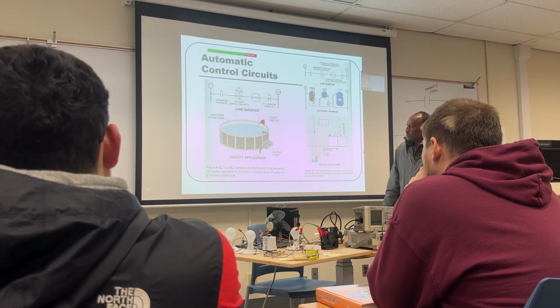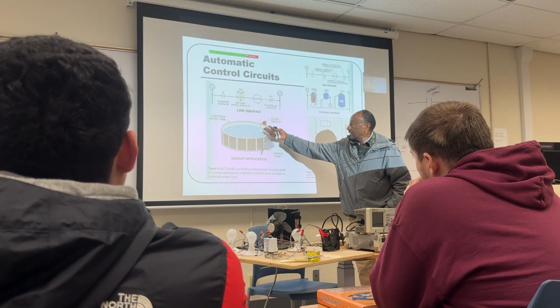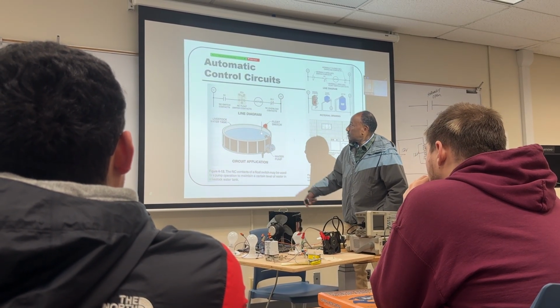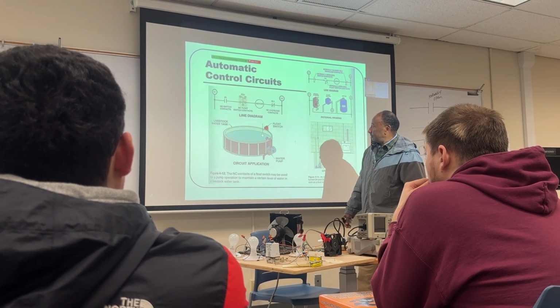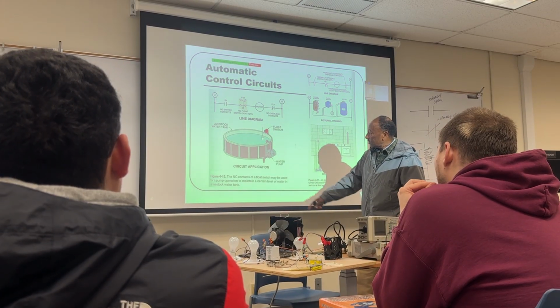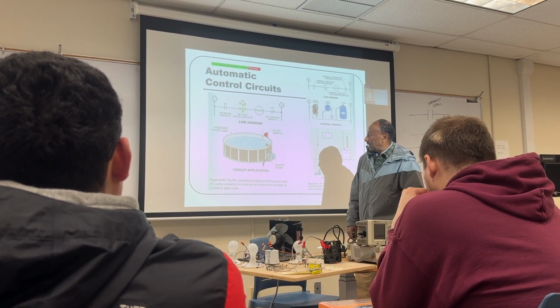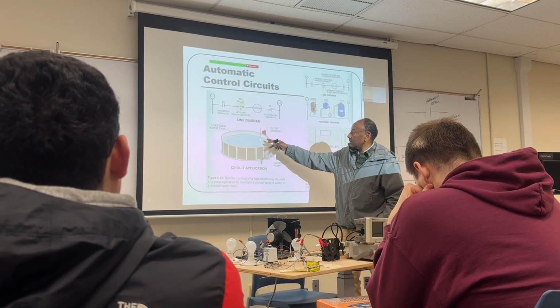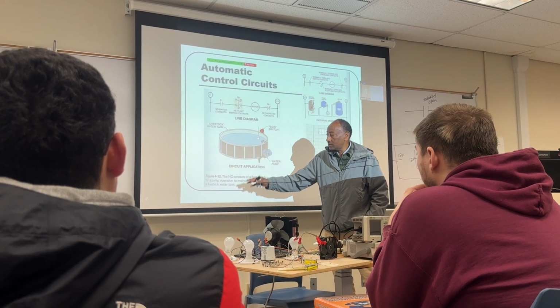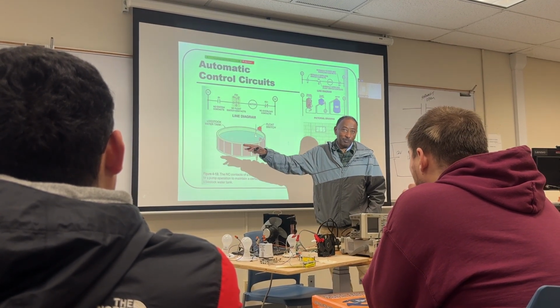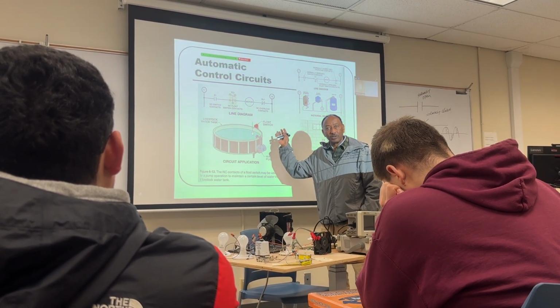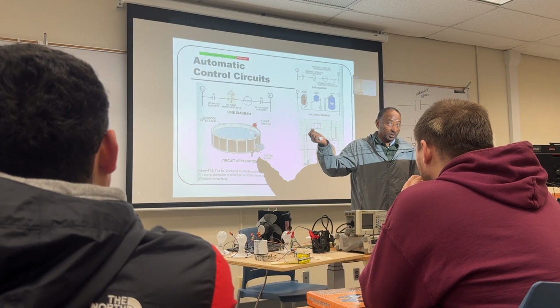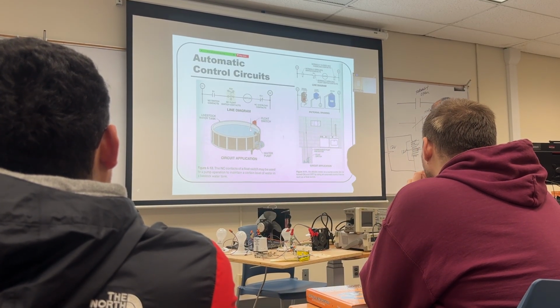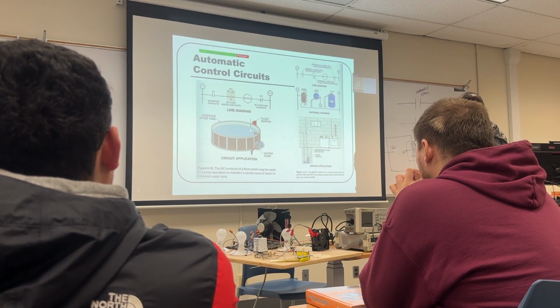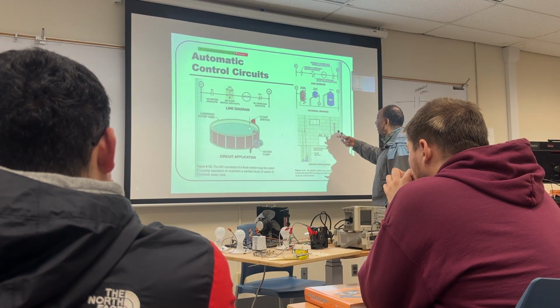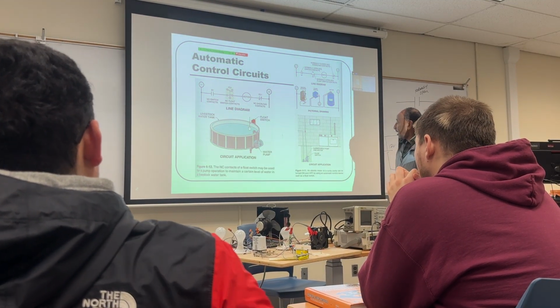So when this reaches a certain point, there is an indicator, so it will turn on the solenoid, which turns on this pump, and then it's empty. This thing will sense, and when the level goes down, it opens the valve and it will pump, and when it reaches a certain point, it will close it. It's automatically controlled without you being there. It's like a float switch. You have that.